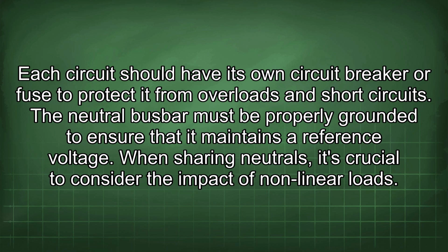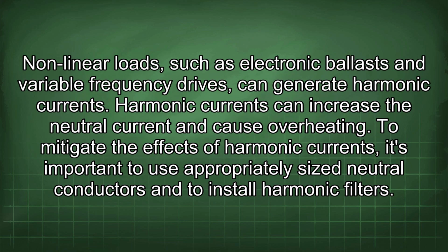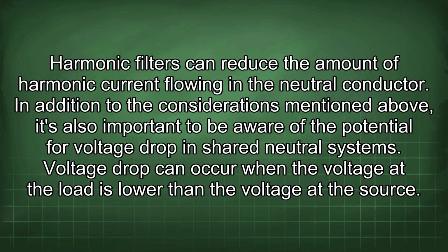When sharing neutrals, it's crucial to consider the impact of nonlinear loads. Nonlinear loads, such as electronic ballasts and variable frequency drives, can generate harmonic currents. Harmonic currents can increase the neutral current and cause overheating. To mitigate the effects of harmonic currents, it's important to use appropriately sized neutral conductors and to install harmonic filters. Harmonic filters can reduce the amount of harmonic current flowing in the neutral conductor.